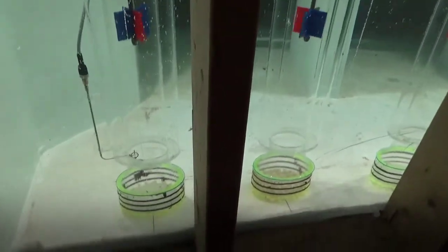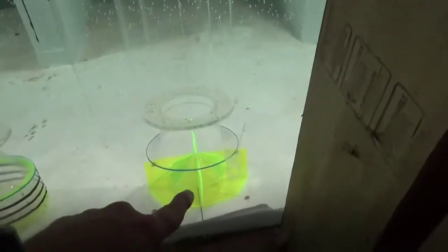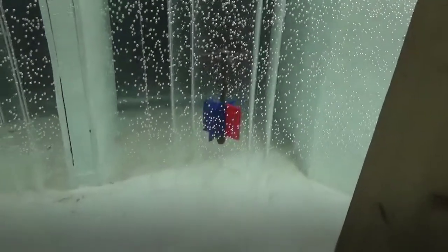And then this one here, it's not moving at all. So the basket's very effective, dissipates the vortices, reduces the pre-swirl to well under a degree compared to this really unsteady, bursty starting and stopping over here. And this helps. As you can see, it's a lot faster, but it's not going to eliminate the vortex activity between them, and it doesn't eliminate pre-swirl low enough.